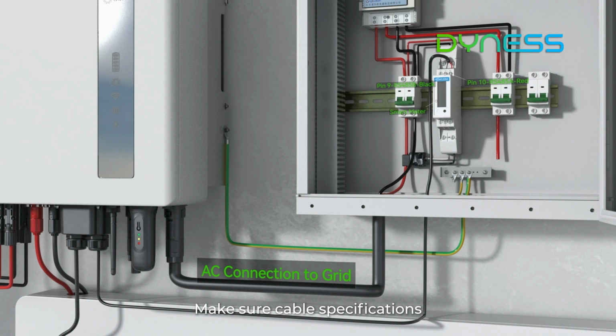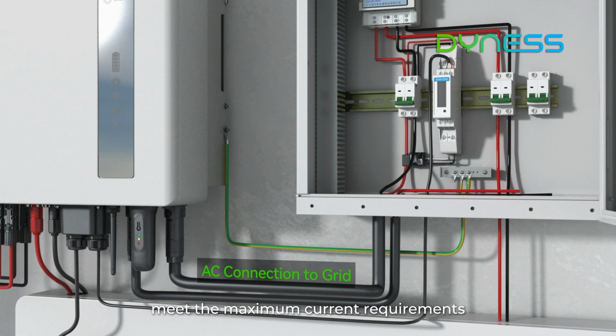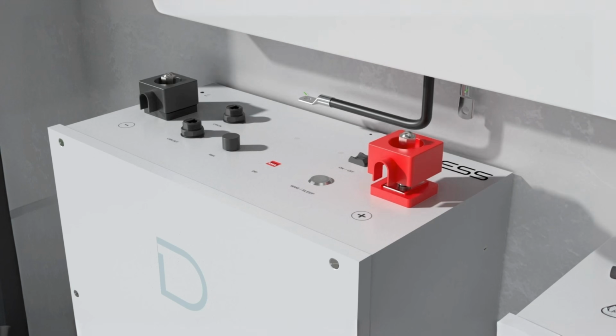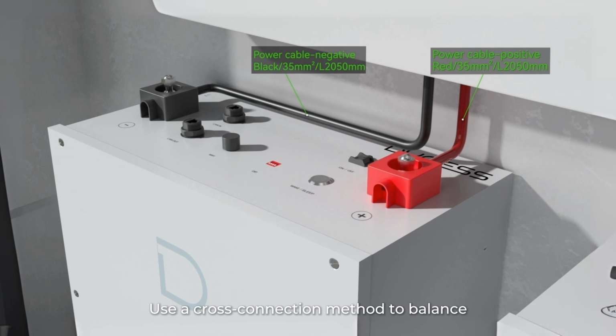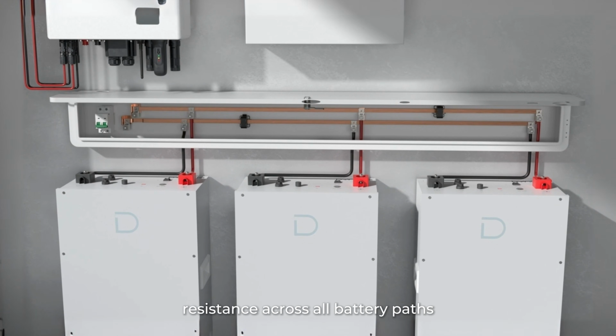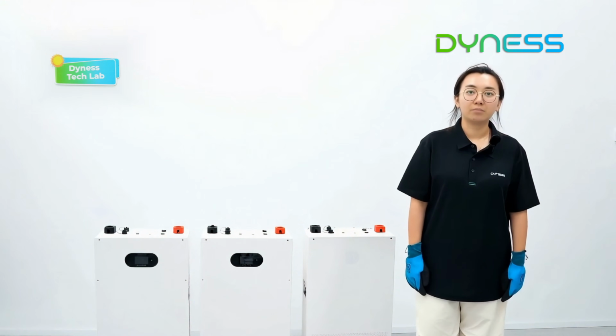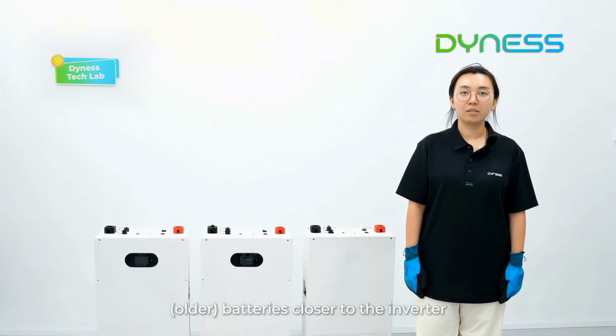Key notes: make sure cable specifications meet the maximum current requirements. Use a cross-connection method to balance resistance across all battery paths. For mixed capacities, place lower capacity, older batteries closer to the inverter to reduce impedance differences.